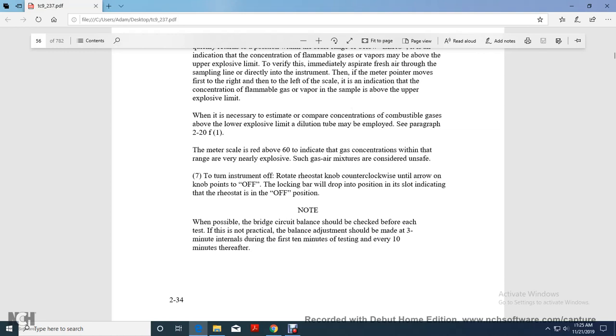Note: the bridge circuit balance should be checked before each of the tests. If it is not balanced, balance adjustments should be made at 3-minute intervals during the first 10 minutes of the testing, and every 10 minutes thereafter.